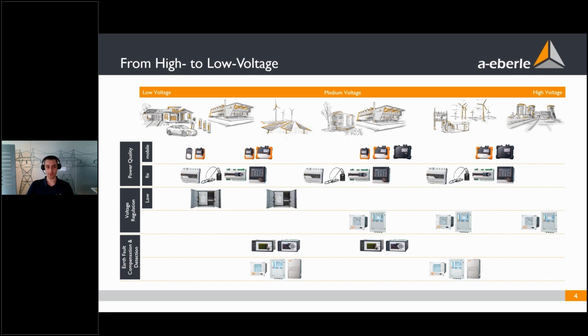And we have earth fault location devices, the EOR-1DS and the, see here, that are mostly used in medium voltage levels. And also the Petersen coil regulator, REC-DP, with its variation REC-DPA, and a few variations of current injection. Here you see the MCI. The Petersen coil regulator is used in a compensated grid to regulate the Petersen coil in order to have minimal or a set point of fault current in case of an earth fault. And our earth fault detection devices are also, of course, earth fault and short circuit oriented.